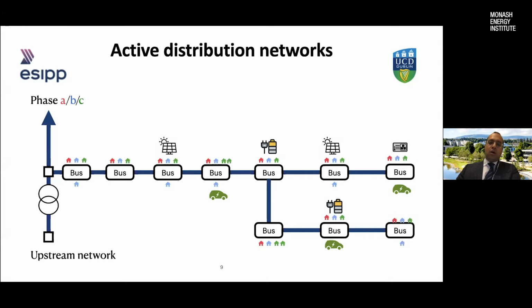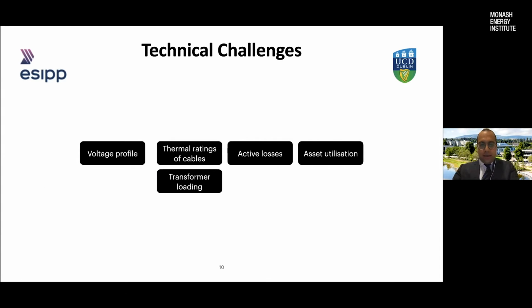So the question is how much reactive power should be injected into the grid, or how much reactive power should be absorbed from the grid, in order to optimize some objective functions. For example, voltage profile, thermal ratings of the cables, active losses, loading of the transformer connecting the distribution network to the upstream network, and also how we can improve asset utilization. That's the key word for many of the utilities. They want to improve how they are utilizing their existing assets. How can they make money using their existing assets without making new investments?